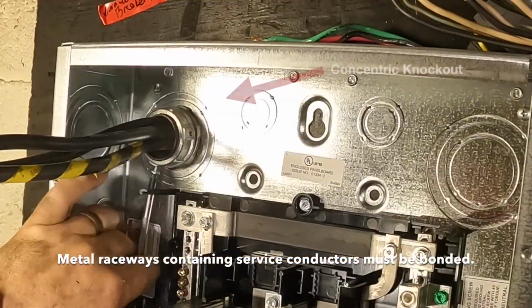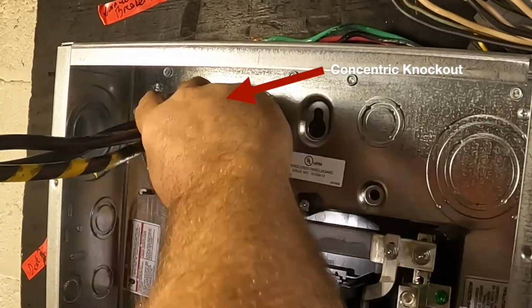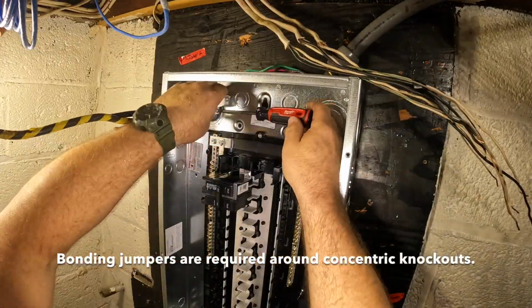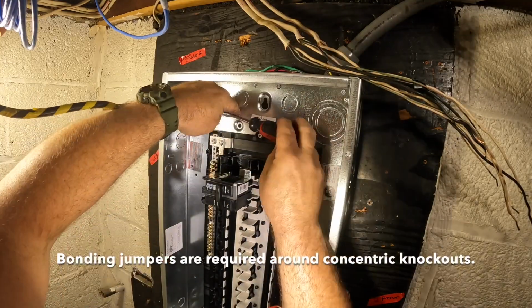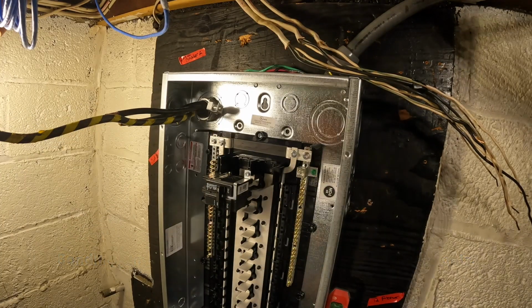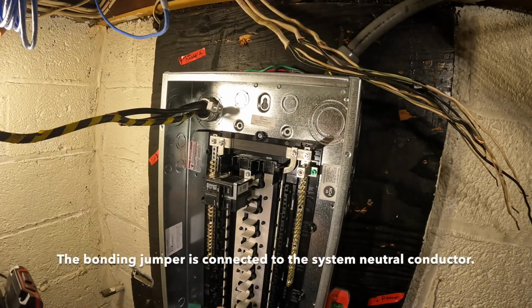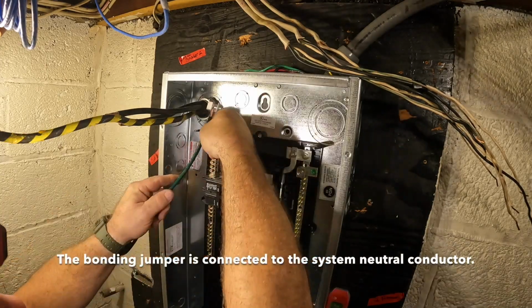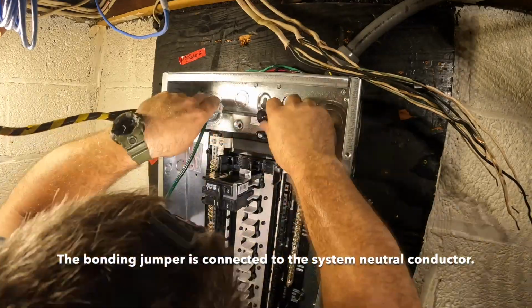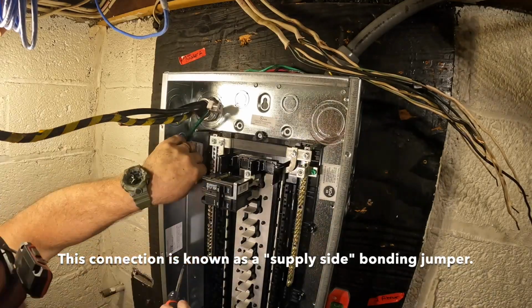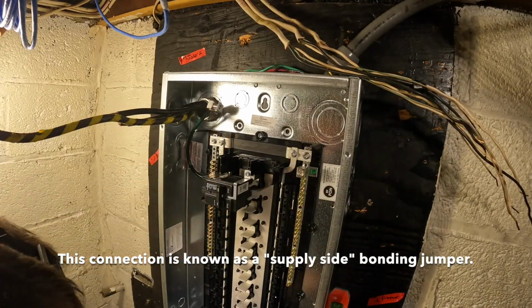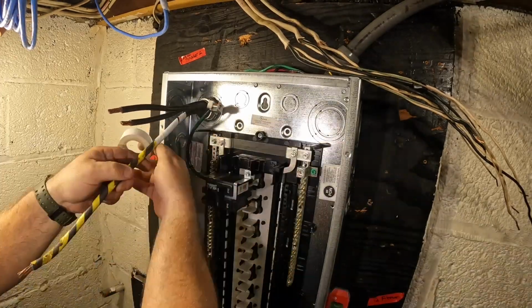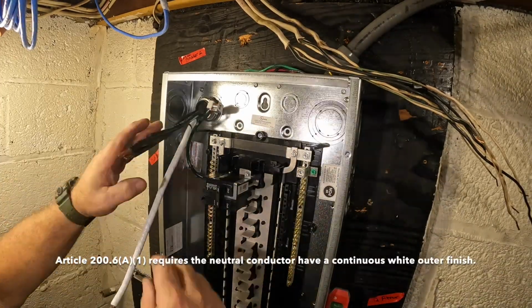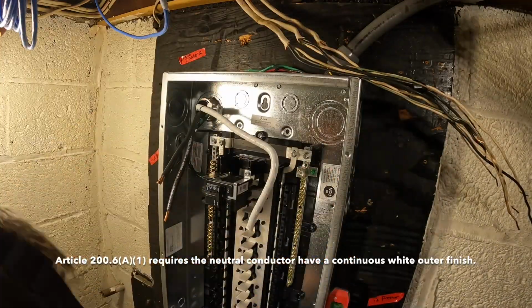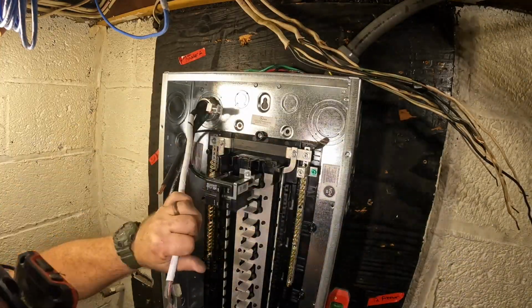So I'm doing some much necessary bonding right here, okay? So that steel pipe, when you do a panel upgrade, it stays the same. If you're doing a service upgrade, that's a complete upgrade, then you would change that. Obviously, if it's steel, it needs to be bonded to the system neutral. And of course, if it's PVC, you don't have to do this, okay? It seems obvious, but PVC is not going to conduct electricity, so therefore it's not going to ever be energized, and so the code says if it's got the possibility to become energized, then it must be bonded. If not, then there's no sense in doing that.